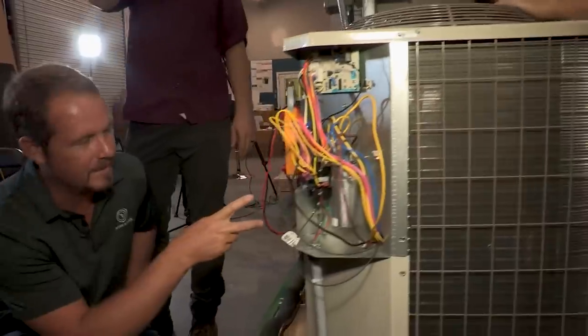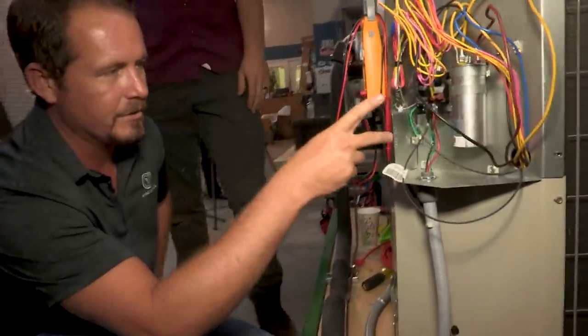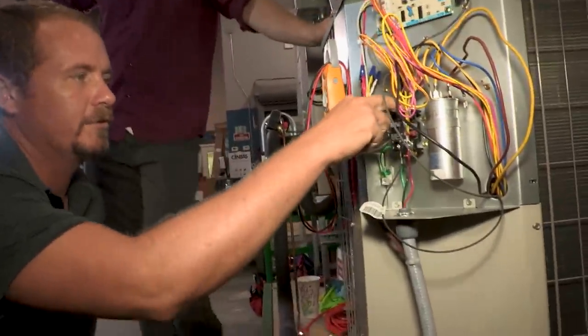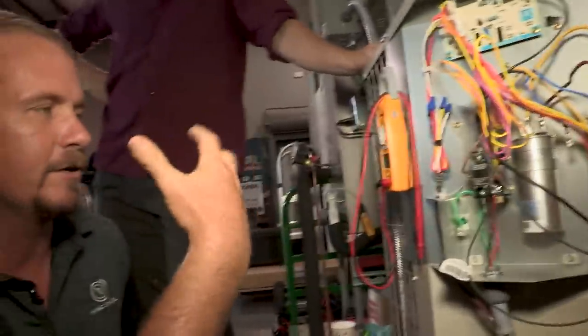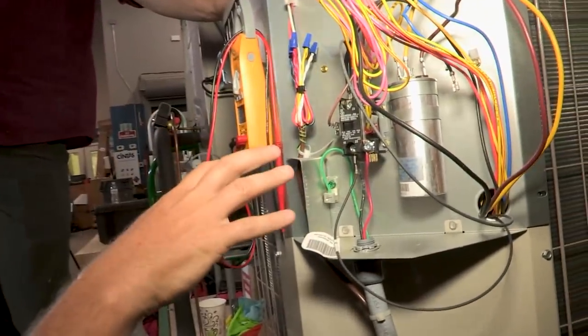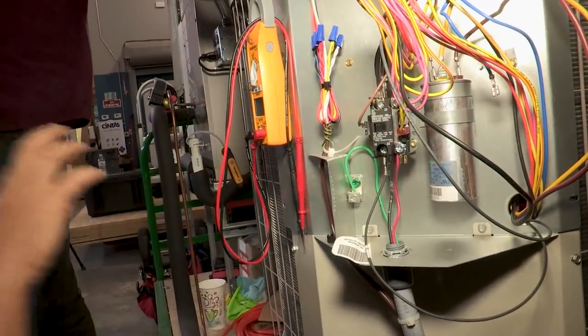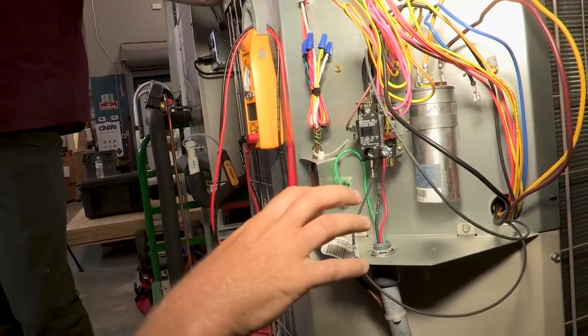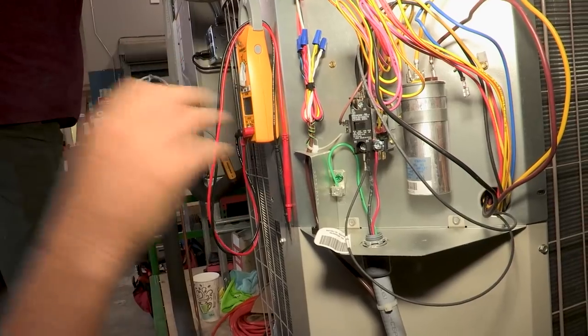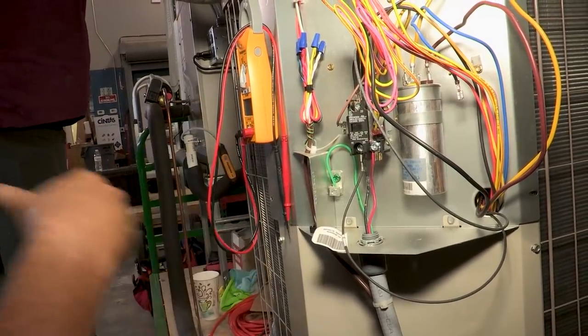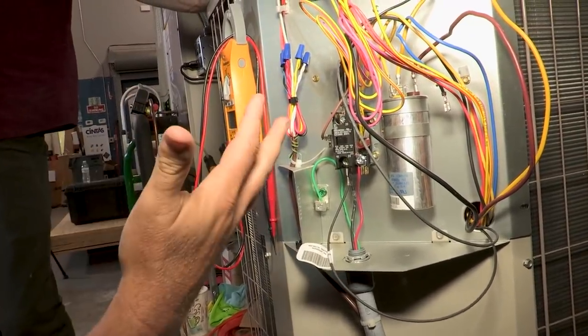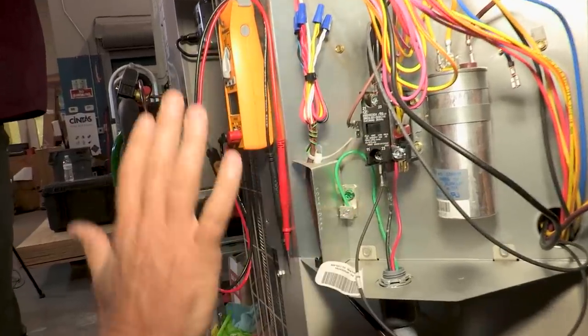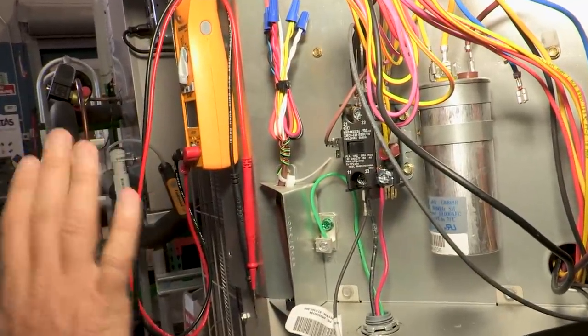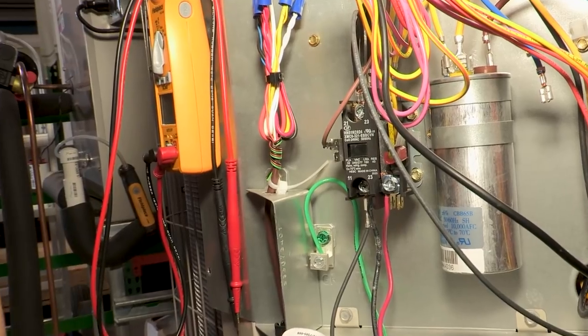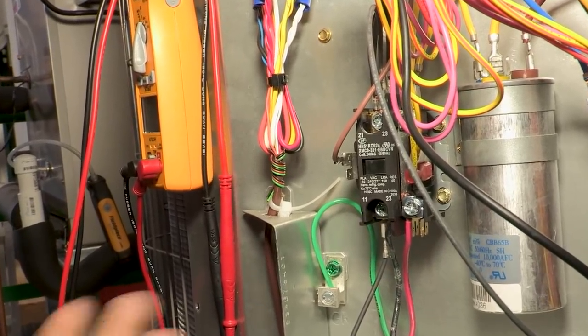People would have made the mistake of not paying attention and connecting them both to the top, because you would think that's how you generally power things up. But in this case, we want the crankcase heater to be energized when the unit's off. Now, we don't have a temperature sensor, so it's automatically going to come on whenever the unit is off. If we had a temperature sensor or a thermostat, that would keep it off for longer, even after it cycled off, based on temperature.